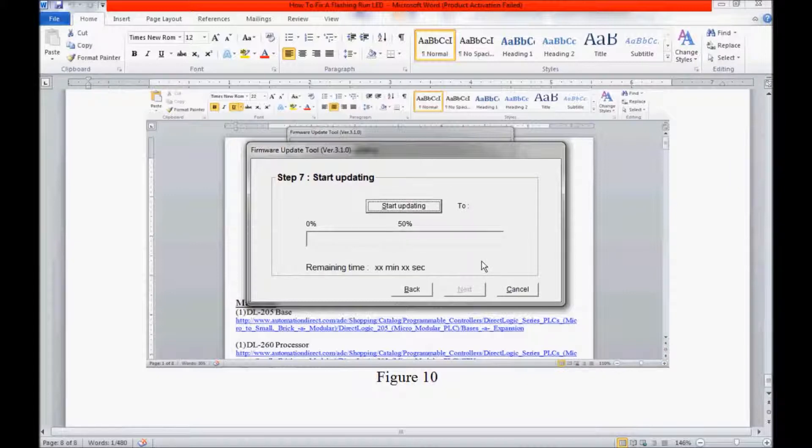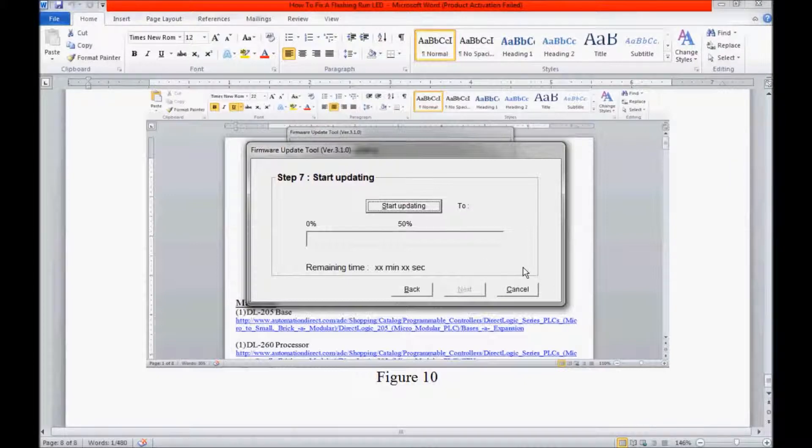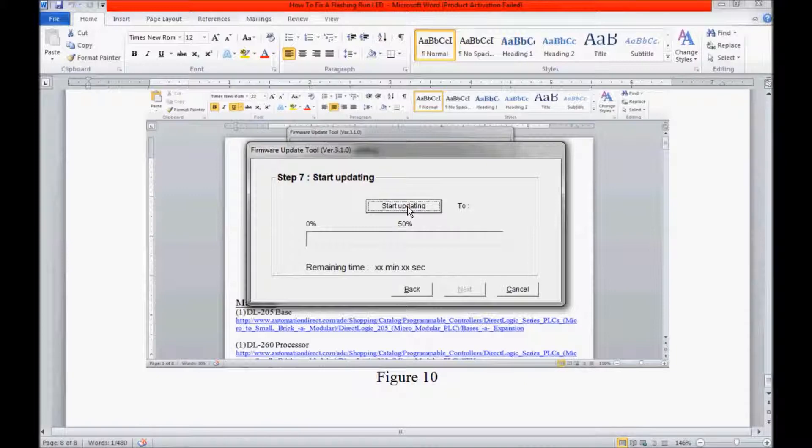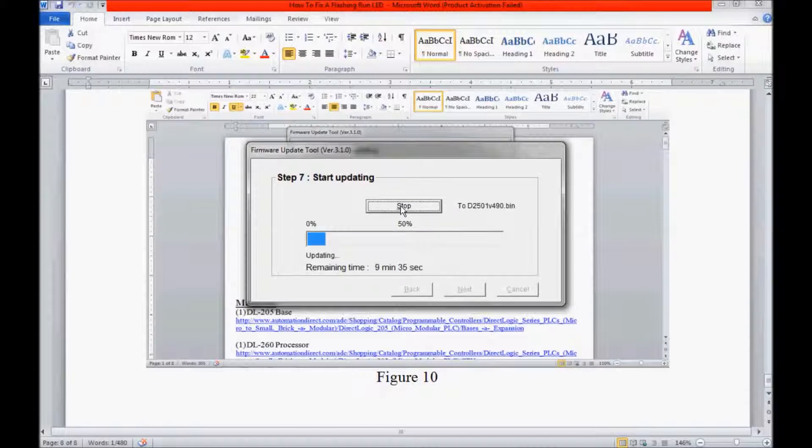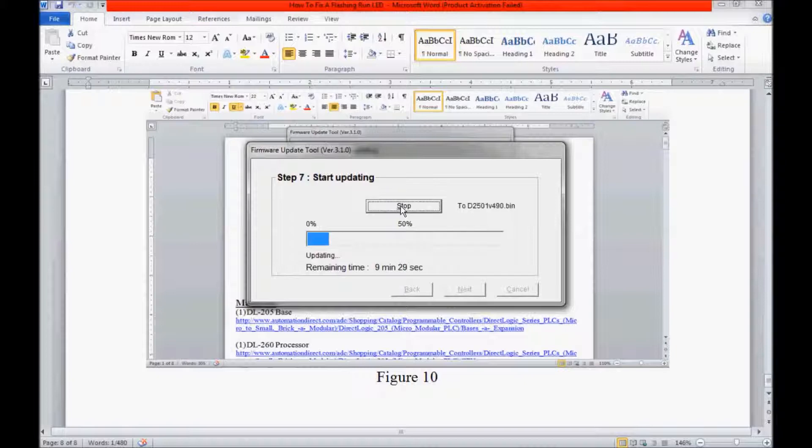Now I am ready to start updating my DL260 processor. I am going to press the Start Update button. What I am expecting to see is a countdown for the remaining minutes and seconds of the download. Also, I should see my RunLED start to flash faster on my processor. So I am going to click Start Update. It takes a few seconds to establish a link. There is my remaining time. It is going to be roughly about 9 or 10 minutes. I will see you back when the download is complete.